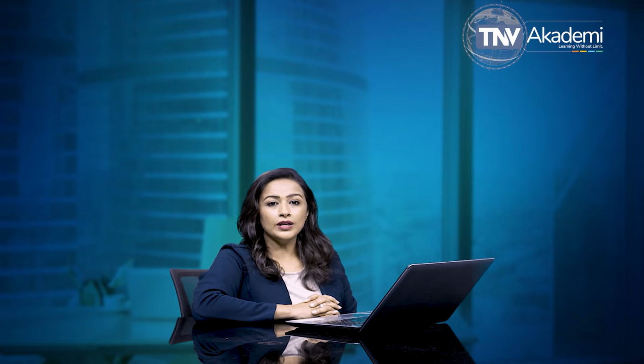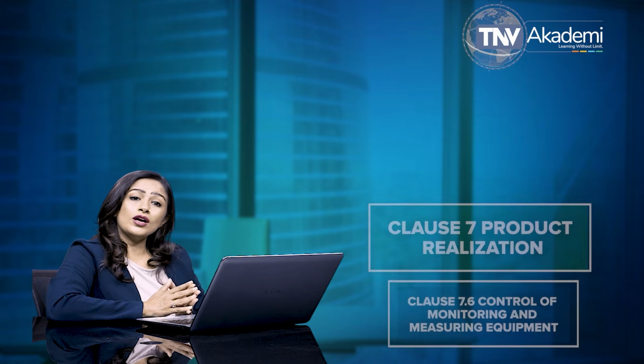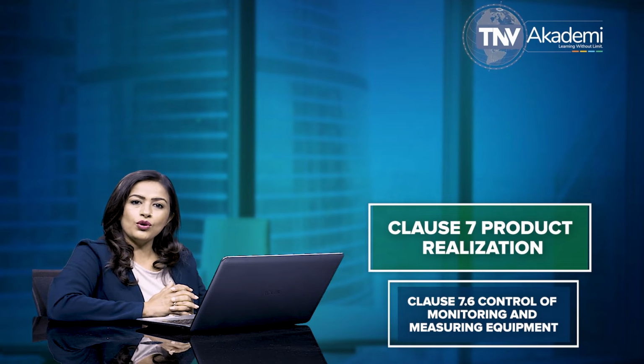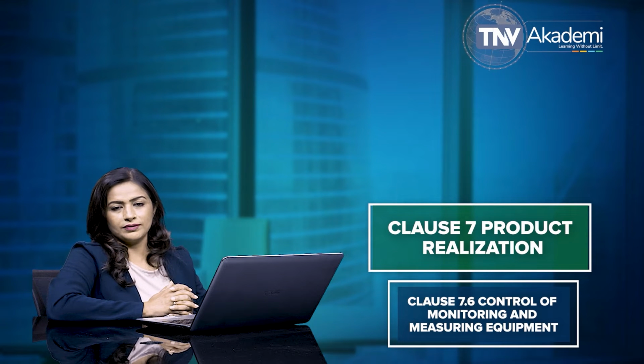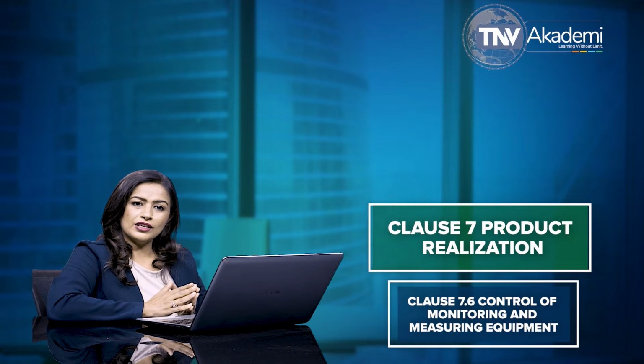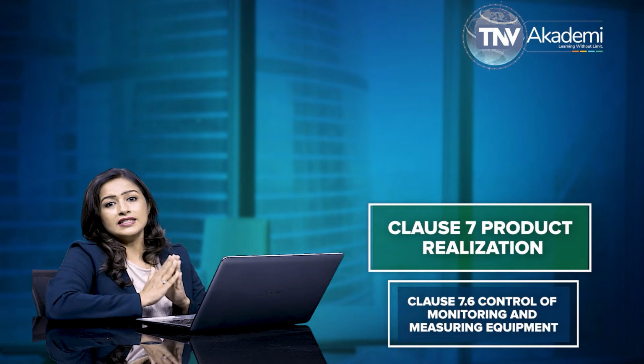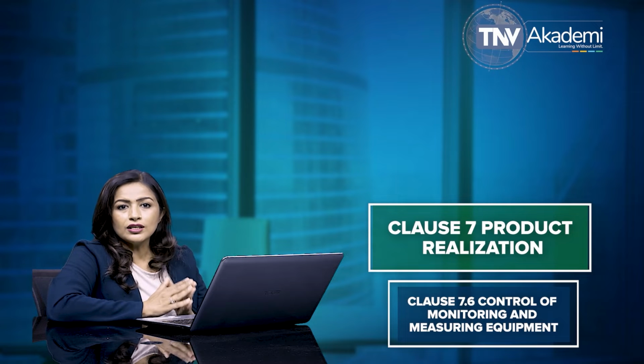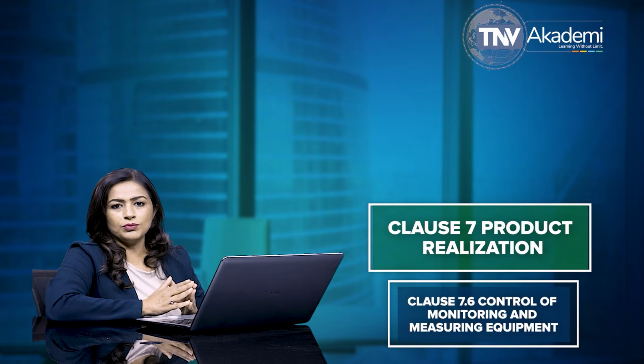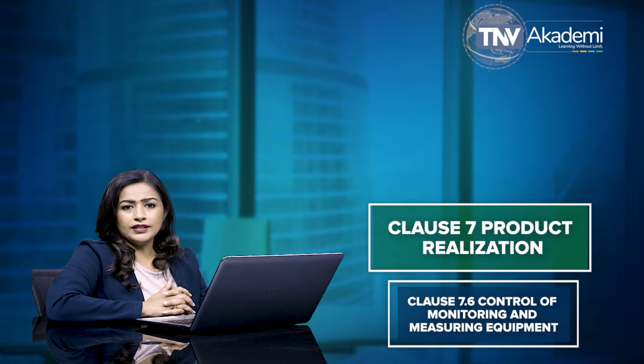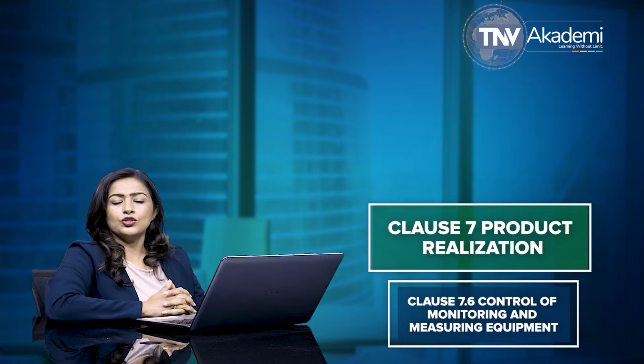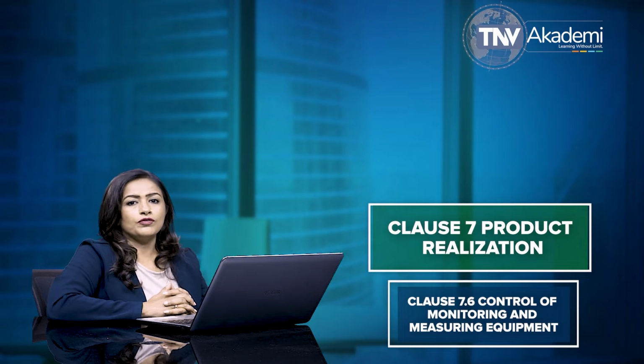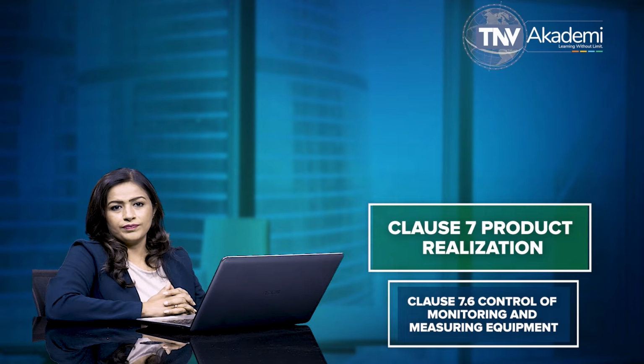In this session, we are going to talk about an international standard, ISO 13485:2016. Now, let us talk about clause 7.6, control of monitoring and measuring equipment. This subclause 7.6 of ISO 13485 states that the organization is required to determine the monitoring and measurement to be undertaken and the monitoring and measuring equipment needed to provide evidence of conformity of product to determined requirements.